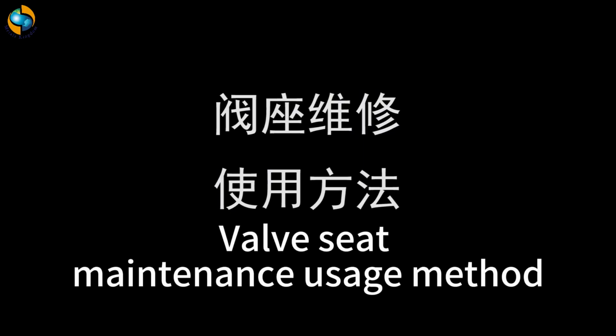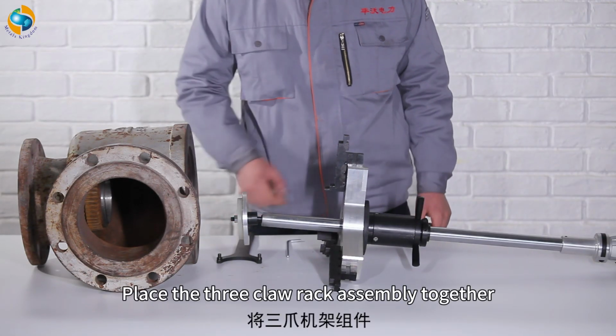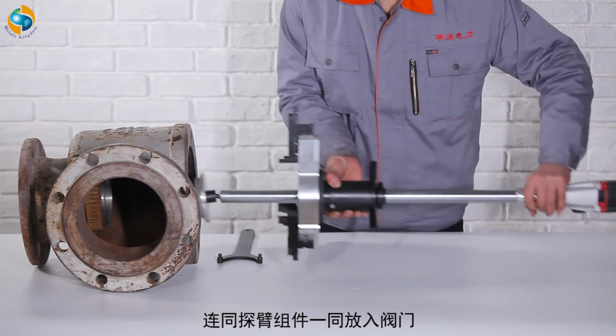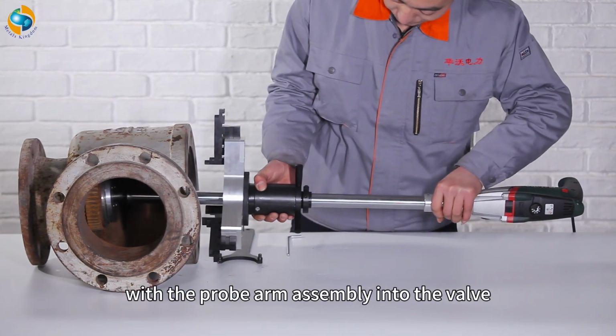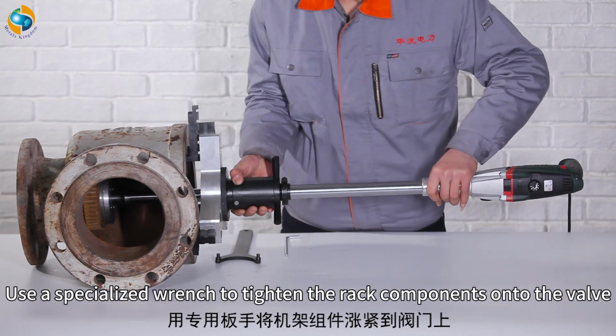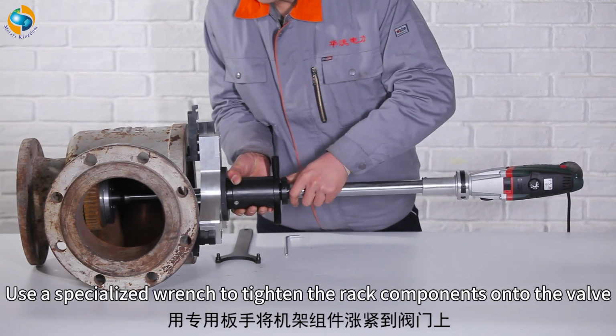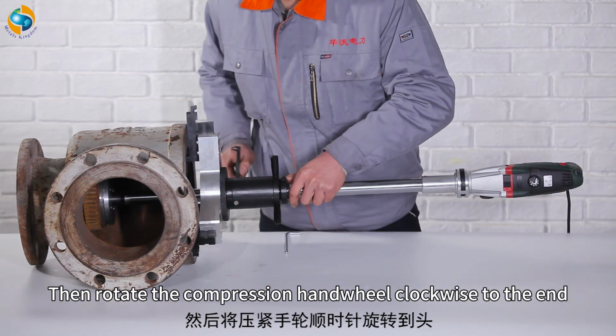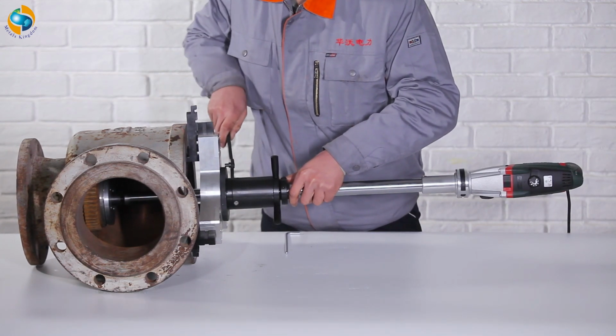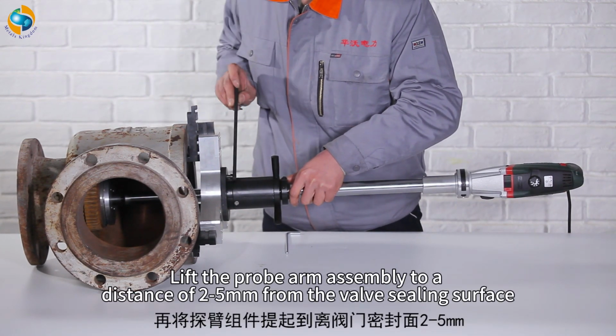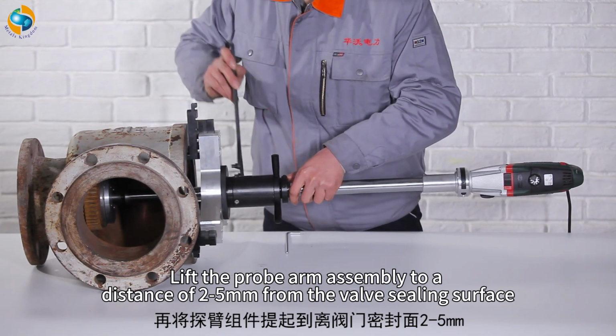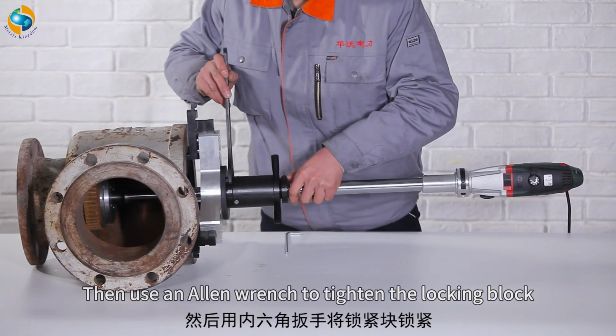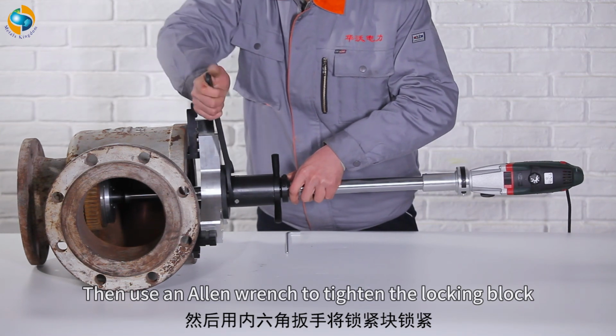Valve seat maintenance usage method. Place the 3-claw rack assembly together with the probe arm assembly into the valve. Use a specialized wrench to tighten the rack components onto the valve. Then rotate the compression handwheel clockwise to the end. Lift the probe arm assembly to a distance of 2 to 5 mm from the valve sealing surface. Then use an Allen wrench to tighten the locking block.